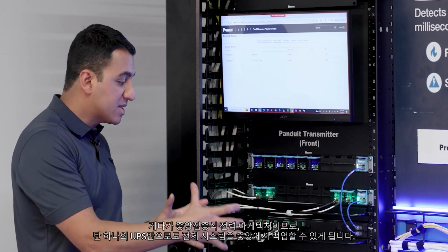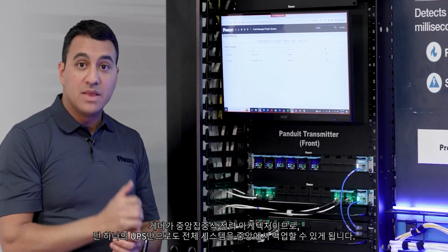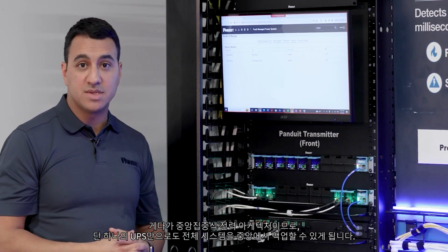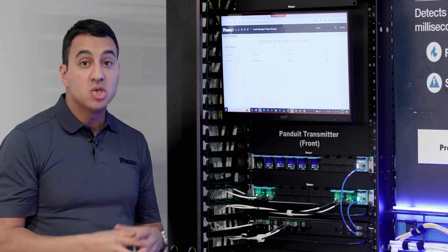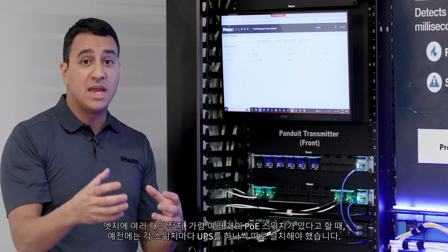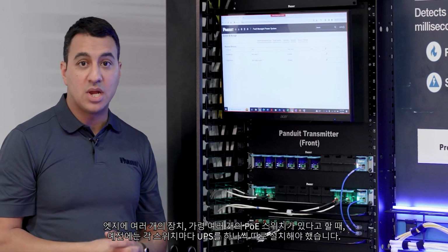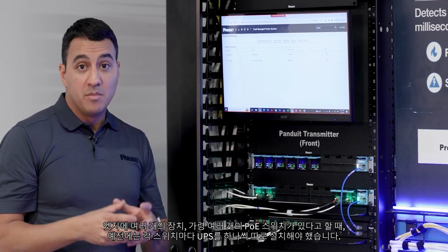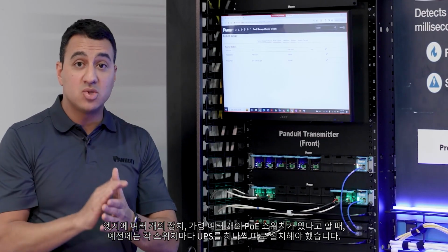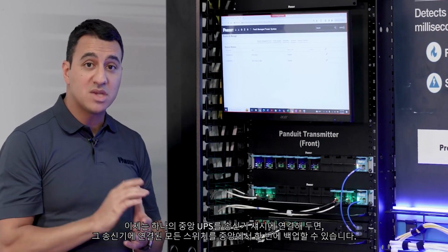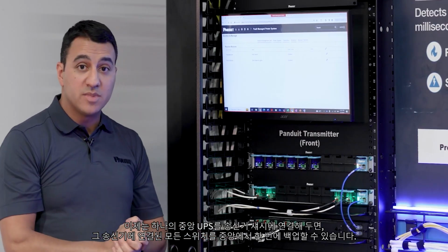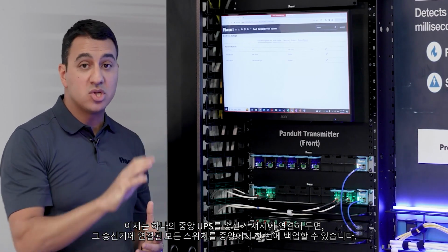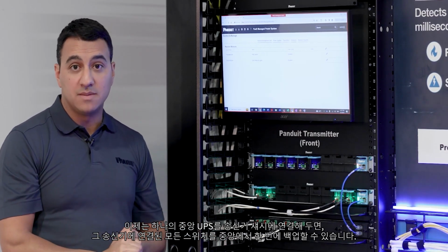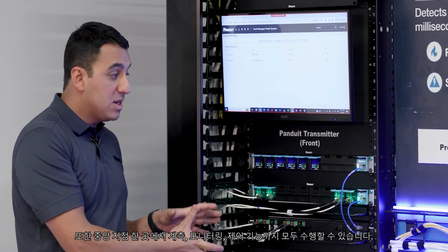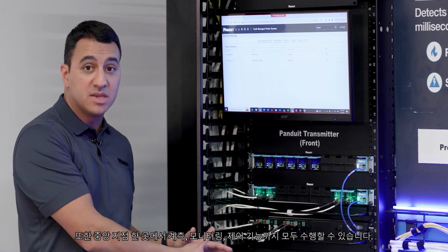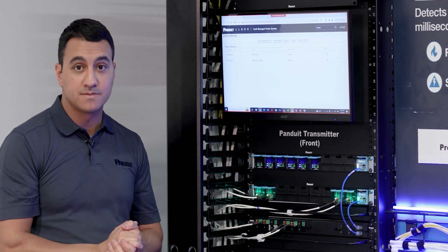But when you think about the centralized power architecture, this allows you to centrally back up your system with a single UPS. So if you had a number of devices at the edge, like a number of PoE switches, and you want to back them up, before you may have to put a UPS next to each switch. Now you can have one central UPS connected to our transmitter chassis, and now every switch that's connected to that is backed up centrally. You also have now metering, monitoring, and control capabilities from one central location.